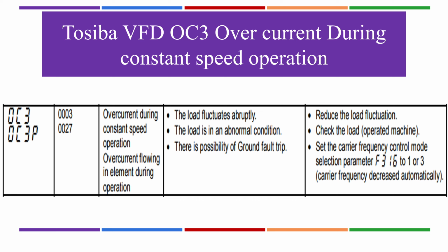There is a CT, current transformer, which reads the current and gives it to the controller, and that is reading the wrong data. So if you check all these reasons and all the parameters I have explained, you will resolve your problem. I expect that most likely, if you check these things only, the problem will be resolved properly.